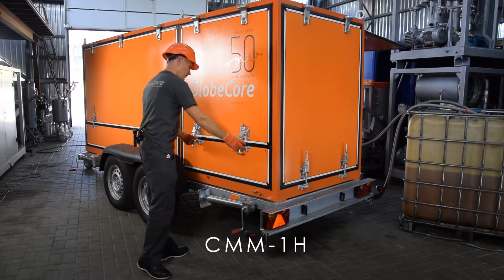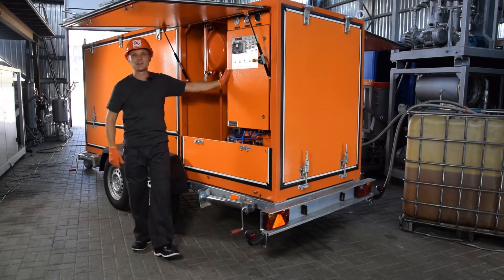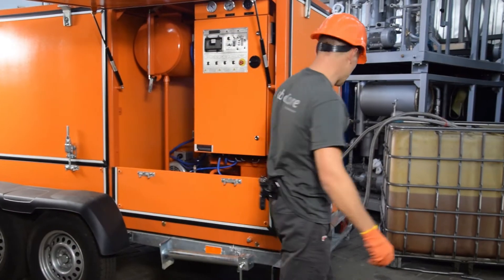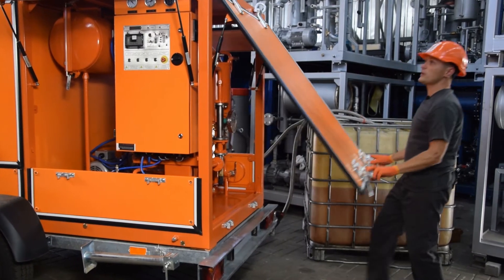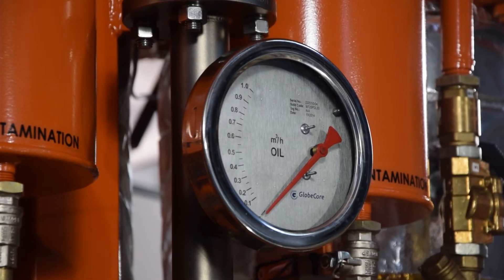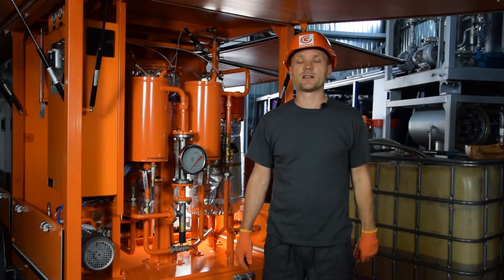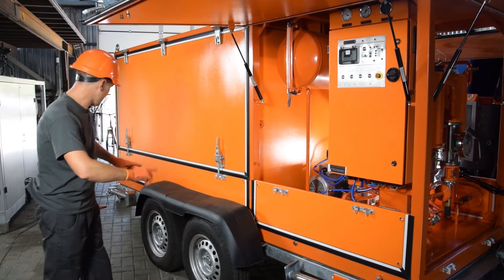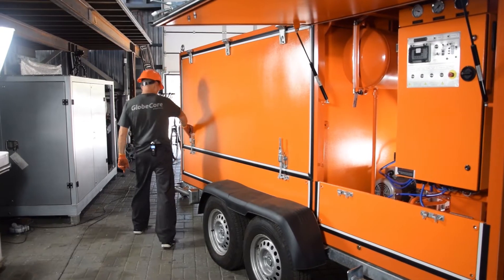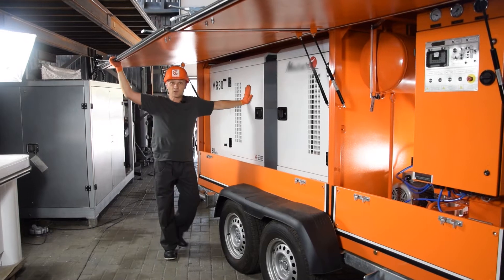This is CMM-1H. The unit is designed for treatment of insulation oils such as transformer and cable oil. The unit provides storage, transfer, filtration, heating and thermo-vacuum drying of insulation oil. The capacity of thermo-vacuum drying is up to 1000 liters per hour, or 250 gallons per hour. The unit is mounted on a trailer and is equipped with a 30 kilowatt generator.